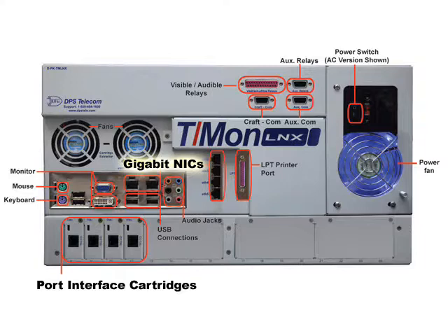This enhances security by allowing you to monitor equipment on multiple networks without routing traffic between those networks. Also on the back panel are 16 cartridge slots for serial interface cards. You'll select different quantities and varieties of these cards to monitor non-LAN devices with interfaces like RS-232, RS-485, 202 modem, and POTS modem. Over 25 protocols are supported. T-Mon LNX can monitor thousands of devices and up to 1 million alarm points, so you have a lot of room to grow. At the same time, it's priced far below the mega-dollar SNMP managers that only the world's biggest companies can possibly justify.